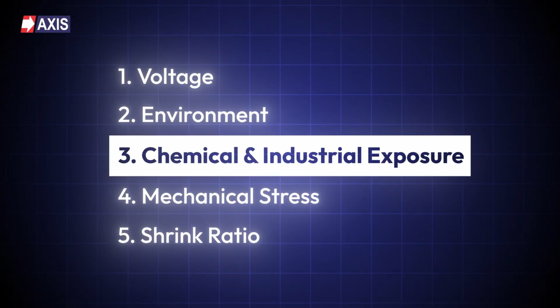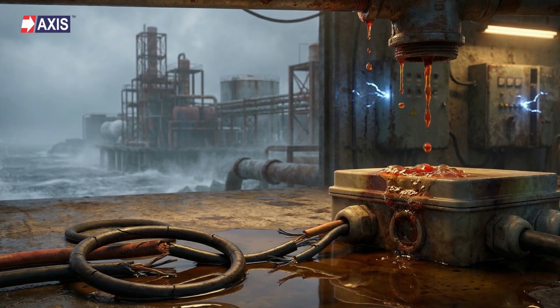Now let's look at the third factor, chemical and industrial exposure. Will your product come in contact with oil, fuel, or industrial chemicals? Some materials swell or degrade in such chemicals. When that happens, they lose grip and sealing strength. If the installation is near coastal areas, salt fog will accelerate corrosion and create a conductive layer on the surface. This increases the risk of tracking under voltage.